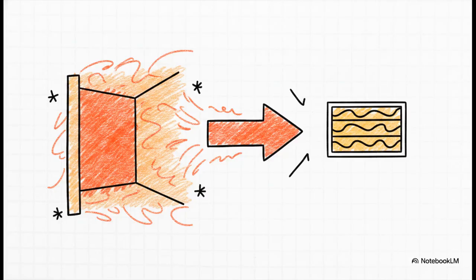Finally, the third big variable is the entering air temperature, or the return air coming back from your room. Picture walking into a sweltering 30-degree room. That heavy initial heat load is going to absolutely force the coil temperature to the higher end of the spectrum. It's going to stay warmer until the room itself finally starts to cool down.